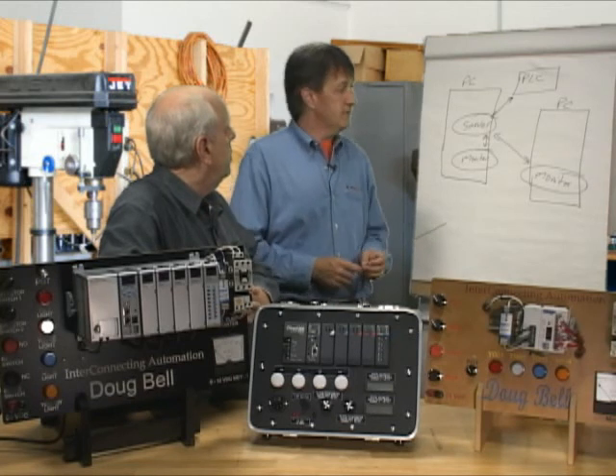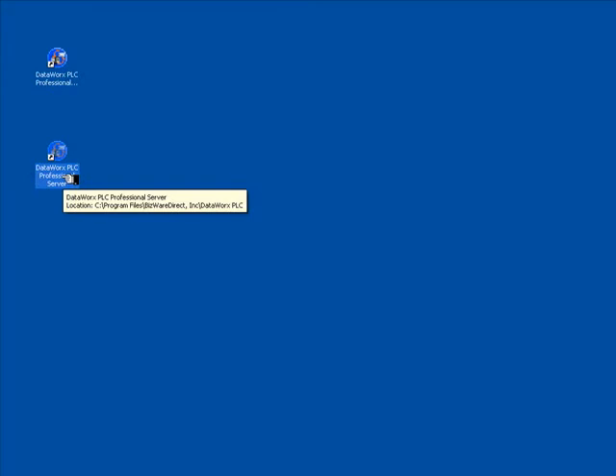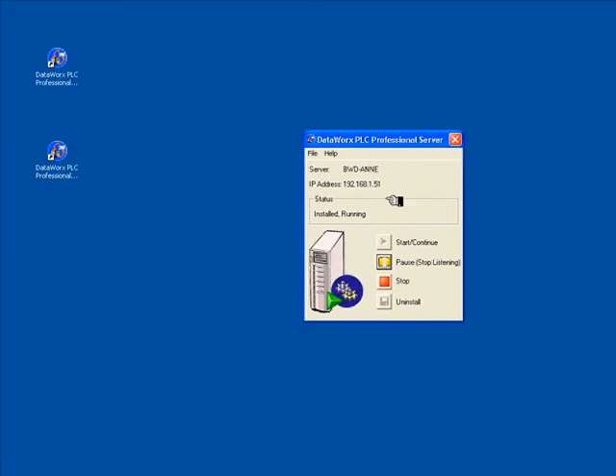We can look at this in more detail on the PC itself. Let's look at the different pieces of DataWorx. We've got two pieces: the monitor and the server. The server is really just a service — an NT service that runs in the background, a Windows process. If you run the server executable you get this little GUI window, which is just an interface to the service. You can see the status: it's installed and running. It tells you the server name of the PC and the IP address of the PC.